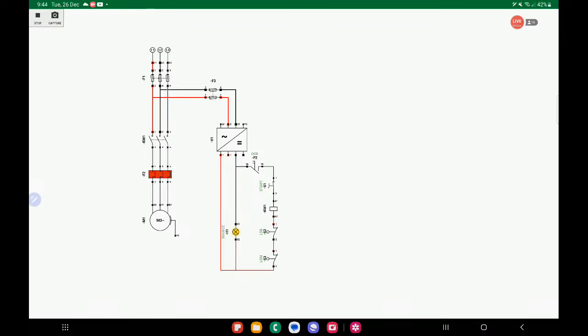So now we need to put an indication light whenever our operator starts retracting. Although this indication light will not be shown on the remote, but on the control panel itself. Because whenever you have trouble, the electrician will always go to the control panel and sometimes will call you to try it and then check. The electrician will check if the run button really is lighting up, so that he will have an idea where he will start the troubleshooting. So we'll put an indication light.